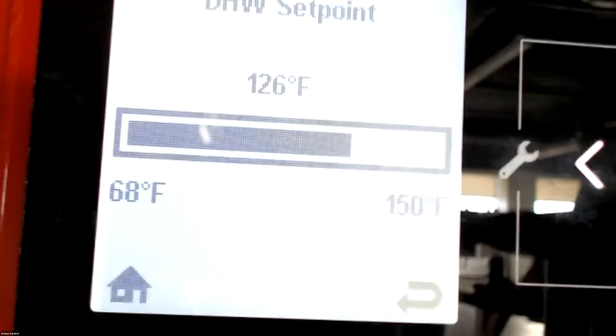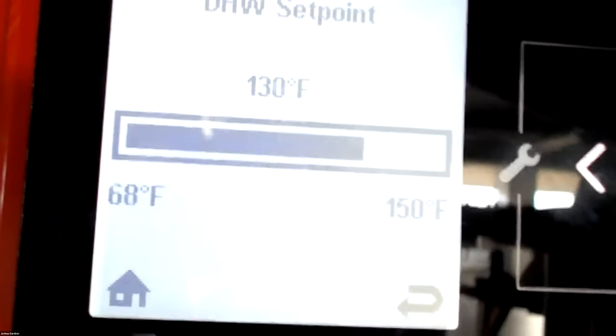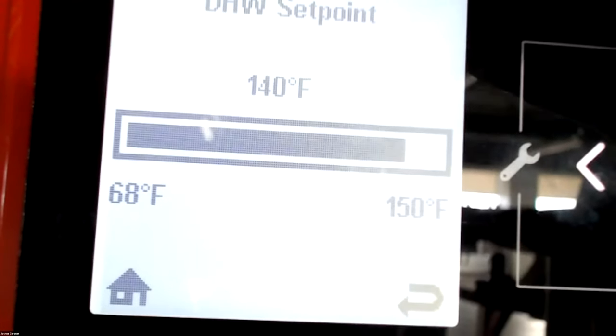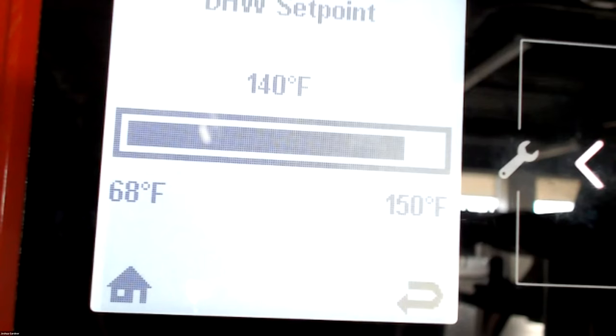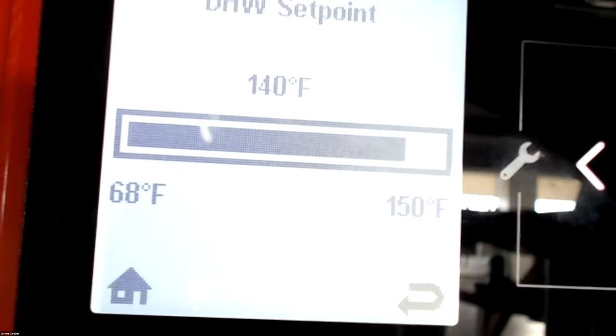We go over to the domestic. This is the combi, so it's going to get right into our set point. This is going to be where our thermostat, our 12K sensor coming out of the supply, what we want that set for. So I got a mixing valve in this one. So what I'm going to do is I'm probably going to bring this up to 140, run it right there. And then I'm going to take my mixing valve and I'm going to bump this down to say 120, 125, depending on my install. Okay.